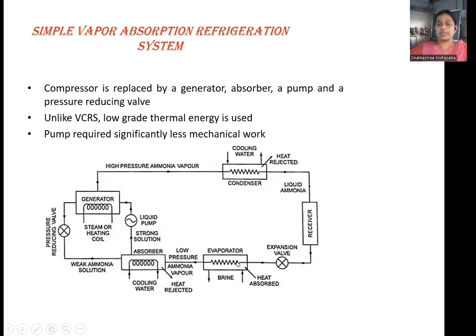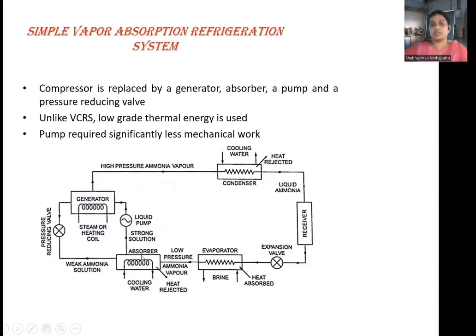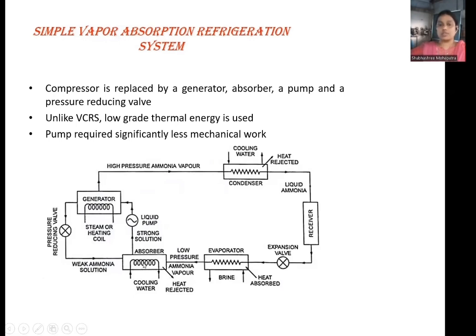At the evaporator, the refrigerant will absorb the latent heat and get evaporated. This vapor refrigerant will get drawn by the absorber. Here the absorbent is present, which draws more and more ammonia, and a strong solution of aqua ammonia is created. As the water absorbs the ammonia, its pressure drops and more ammonia is drawn from the evaporator. Thus, a strong solution is prepared at the absorber.